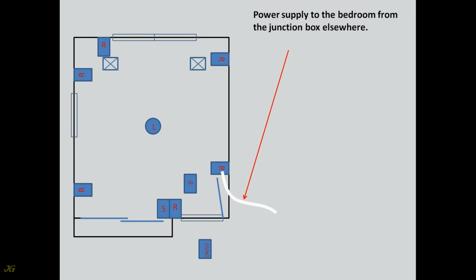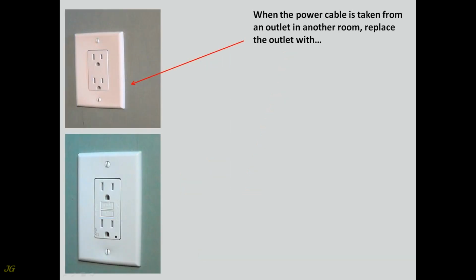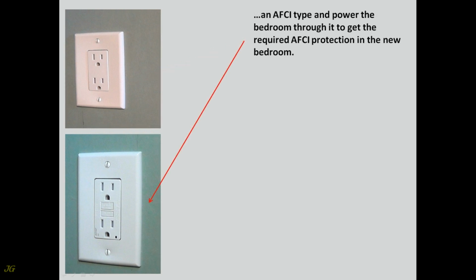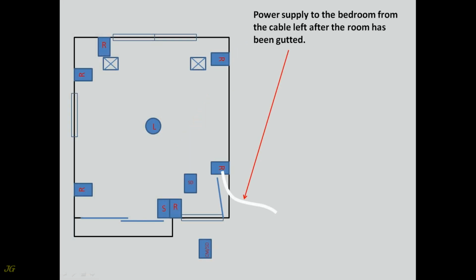Power supply to the bedroom from the junction box elsewhere. When the power cable is taken from an outlet in another room, replace the outlet with an AFCI type and power the bedroom through it to get the required AFCI protection in the new bedroom. Power supply to the bedroom from the cable left after the room has been gutted. When the power cable is left after the room has been gutted, an AFCI-type receptacle should be installed in the first outlet in the bedroom and used to power the bedroom to ensure the required protection of the entire room.